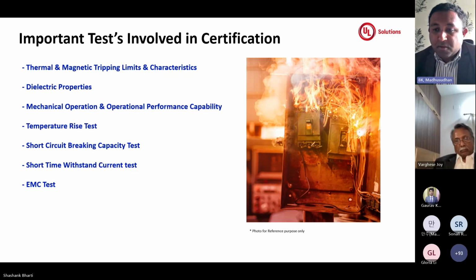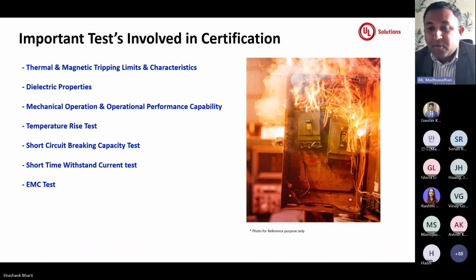Basically, this test speaks more about the dielectric withstand test on different configurations of the poles and the breaker. Normally, it will be done on terminals, two terminals, breaker in off position, breaker in trip position, and with breaker in on position with all poles connected together with the frame and also with grounding. And in addition to that, for high voltage testing, an impulse test is carried out under sequence 1 to see that when an impulse voltage is applied across the breakers for different configurations, there should not be any flashover or breakdown due to failure of the contacts or the live parts.